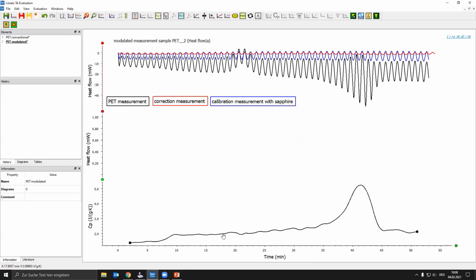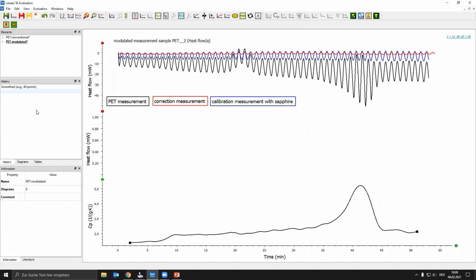So what's possible with every software, I think, is you can smooth these curves just for better or clearer results. Basically, you can see everything here. There's the rise of the Cp due to the glass transition and also the melting. And now let's smooth it. And what you have to keep in mind, if you smooth the curve, you also change the result. So, for example, if you want to smooth over 300 points in this case, you won't see the glass transition anymore. So it's important to use the right smoothing just to make sure you don't change the transitions you can see here on your signal.